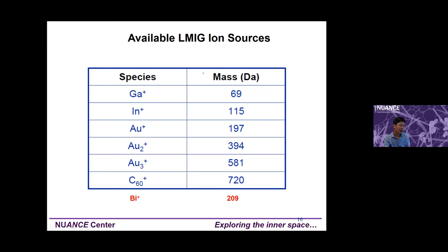The primary ion source often used in our ToF-SIMS is gallium-69. Some instruments use gold, indium, or C60. Newer instruments mostly use bismuth clusters. Gallium-69 is smaller compared to other primary ions, which is an advantage — it is easier to focus and gives much better spatial resolution for mapping. However, because it is small and high energy, it causes more damage, making it harder to get higher mass fragments. With our gallium source we mostly get fragments up to about 200–300 mass units. With bismuth you can get up to 500–600, so most new instruments now use bismuth.